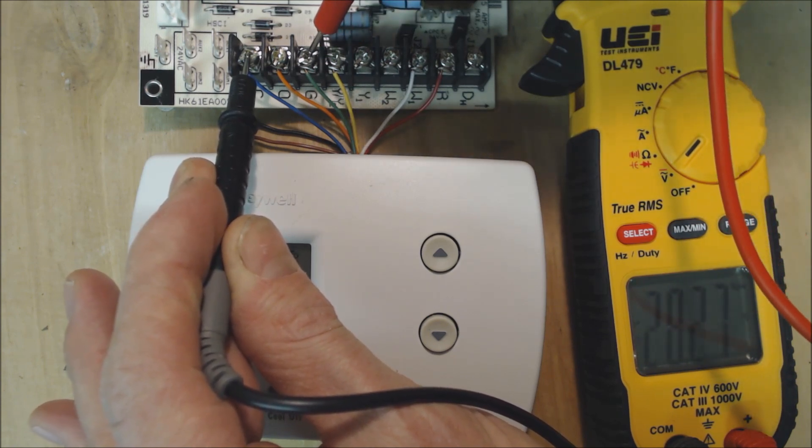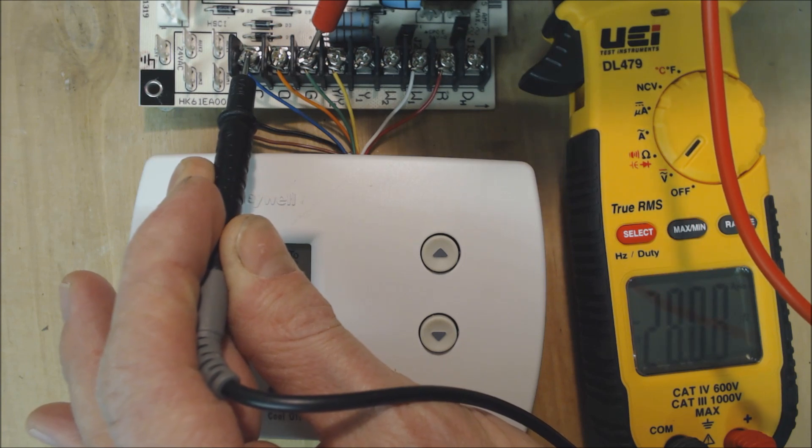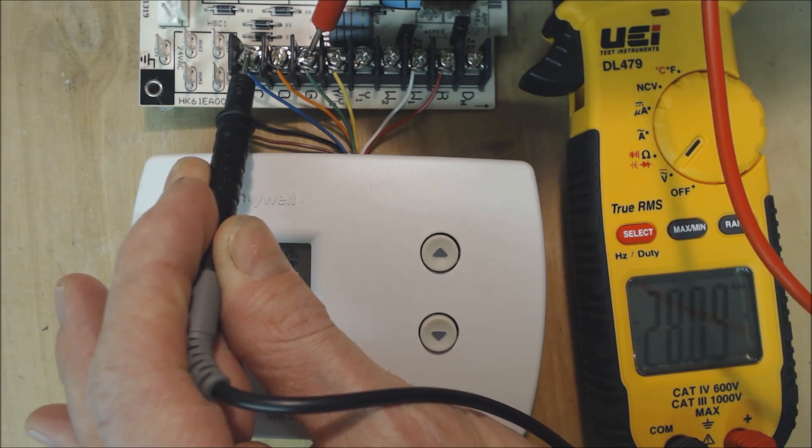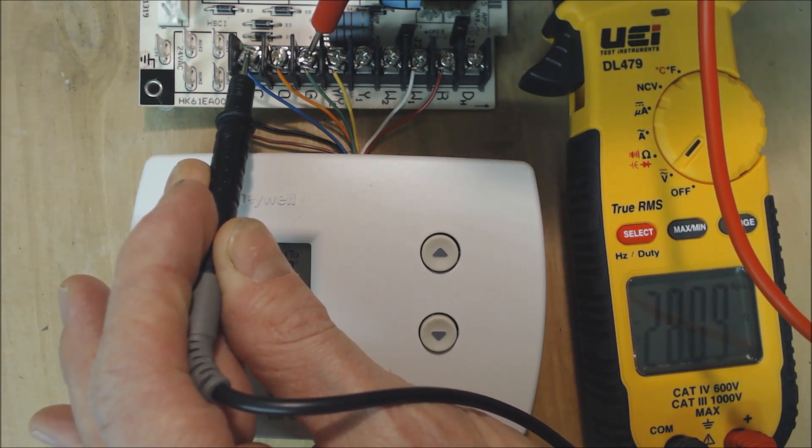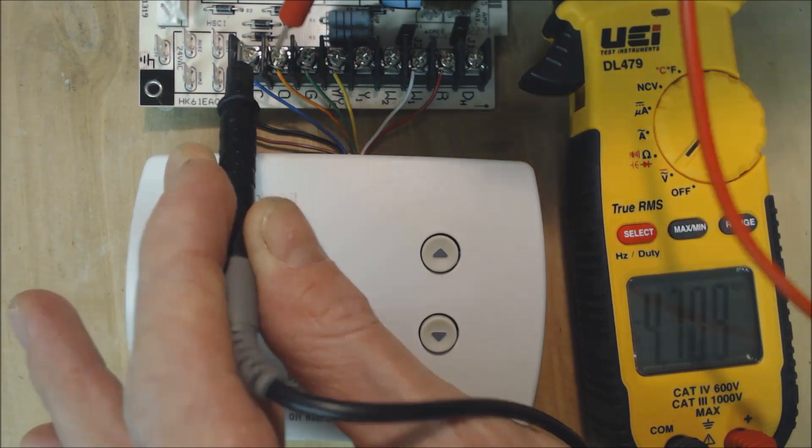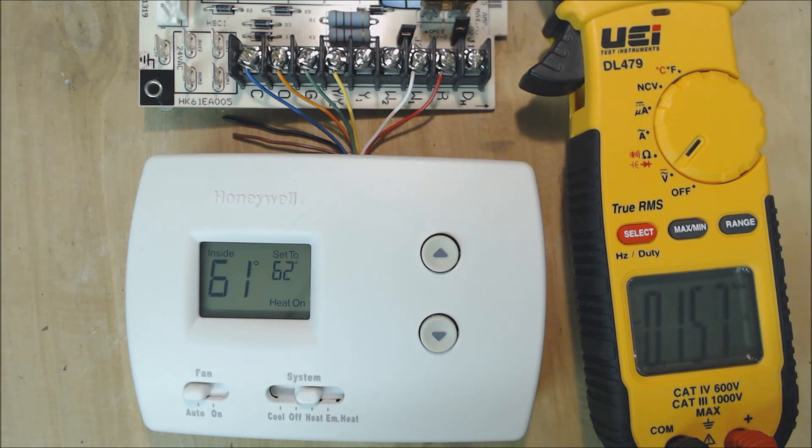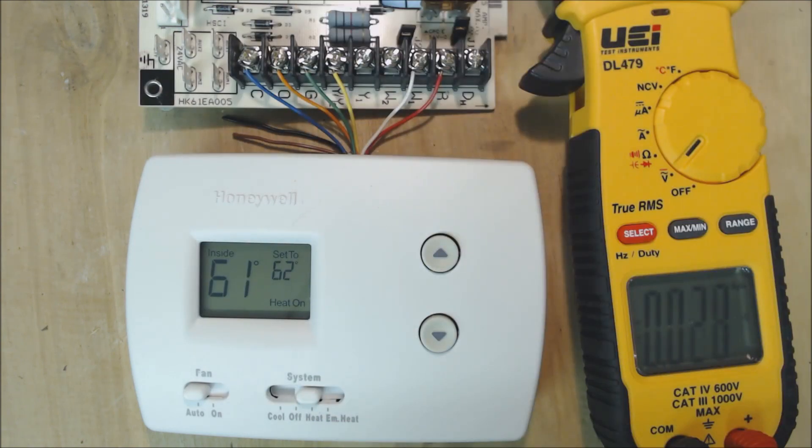Also, if we put our probe on G, we got 28 volts. We are presently calling for heat and that is correct. We should not have any voltage on the O right now. That means we don't have our 24 volts on the O, and that is correct. The thermostat is sending voltage correctly to the indoor control board.